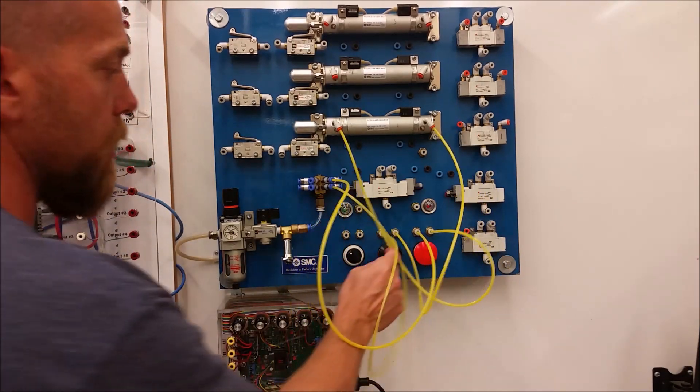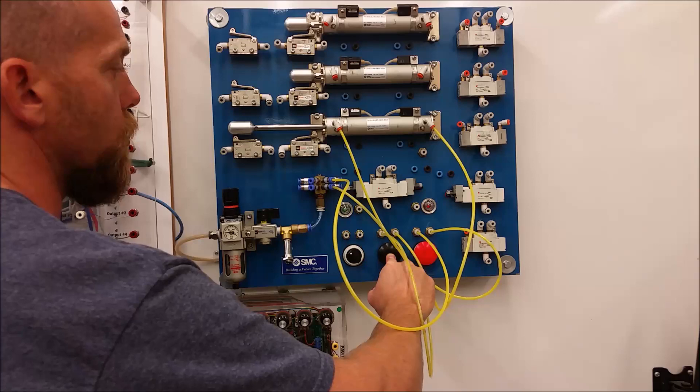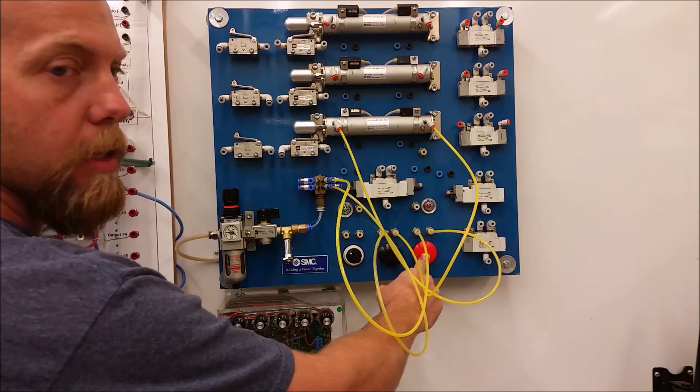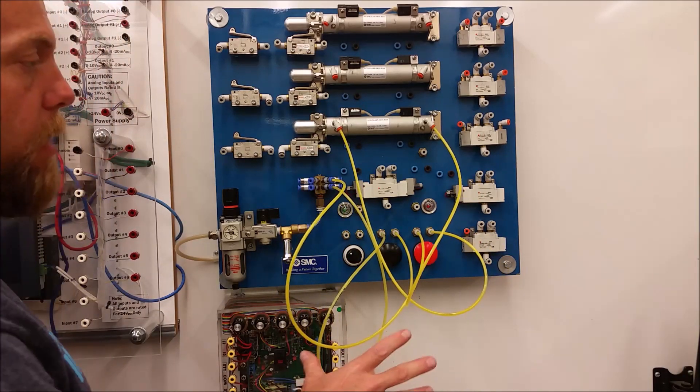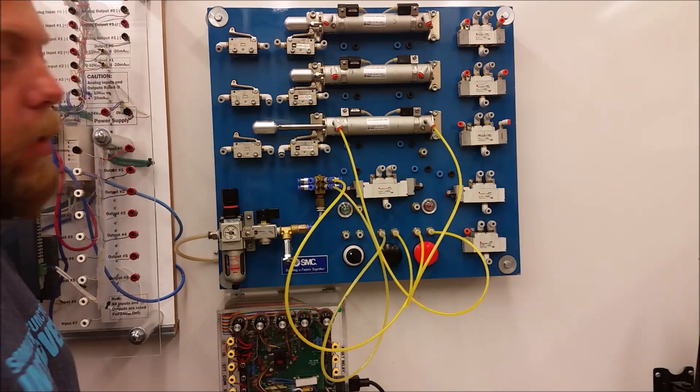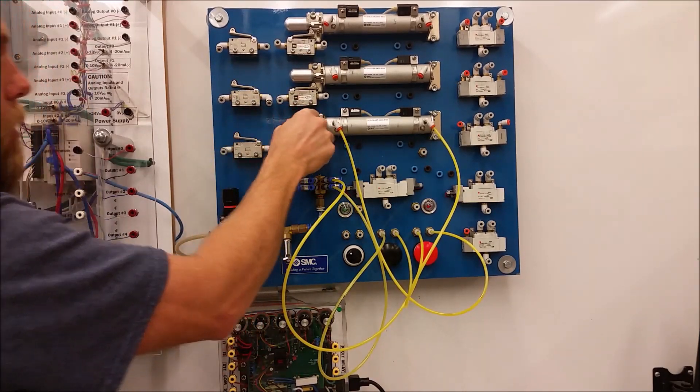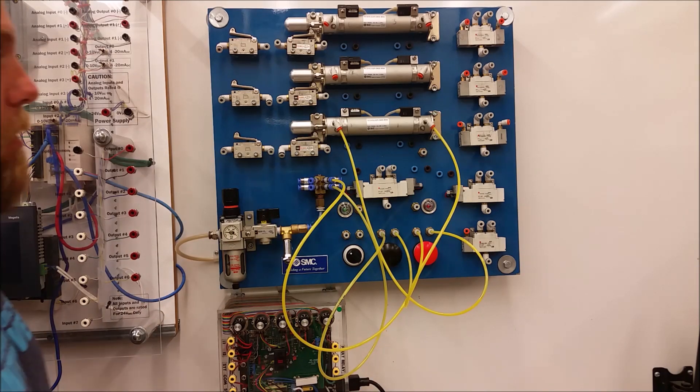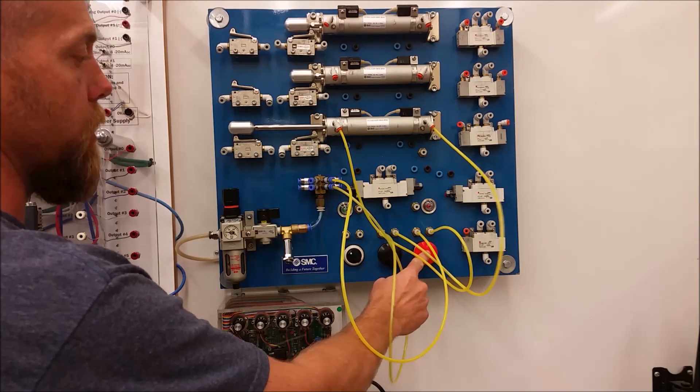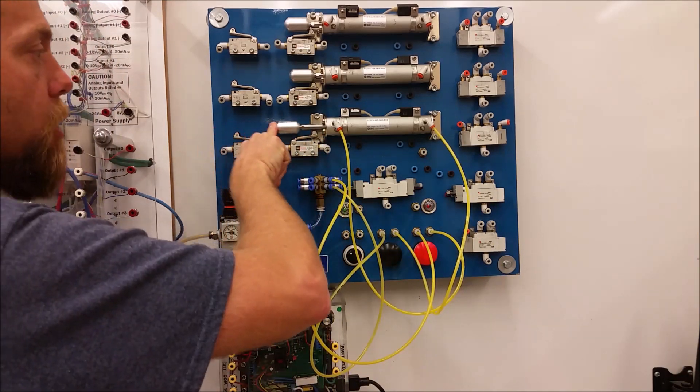One thing to notice though is that if I just tap this guy, it doesn't go all the way. I have to keep pushing this in order for it to extend all the way. If I hit this guy, it only goes halfway. I have to keep pressing it to retract. So there's a better way to do this. We can incorporate one of these 5-2s. And then as soon as I trigger the push button, then it's going to go to that position. You can see here that I can move this double-action cylinder wherever I want. Once we make use of the 5-2, then it will be maintained so that I just have to tap the push button.